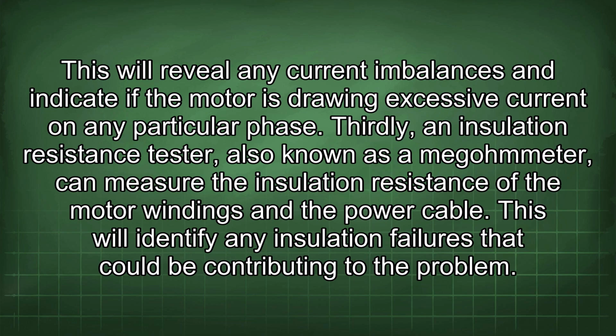Thirdly, an insulation resistance tester, also known as a megohmmeter, can measure the insulation resistance of the motor windings and the power cable. This will identify any insulation failures that could be contributing to the problem.